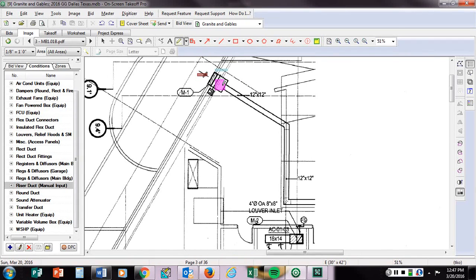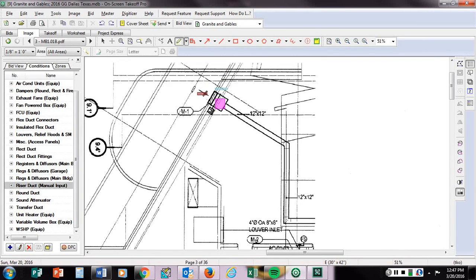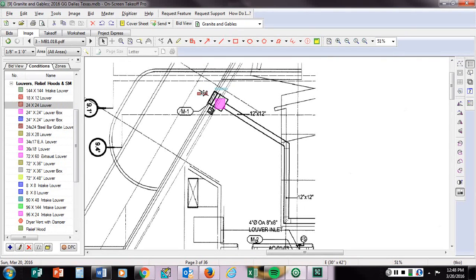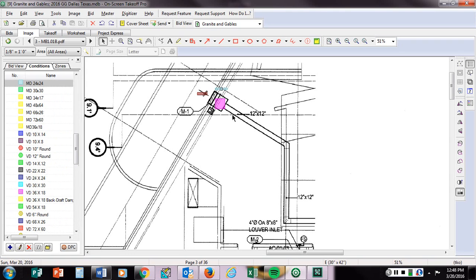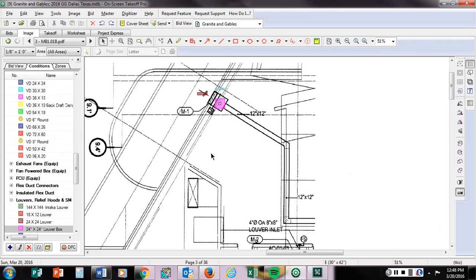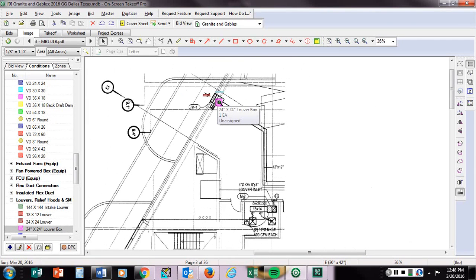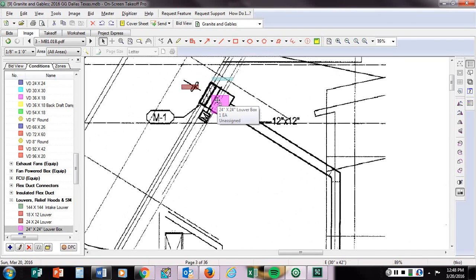Here we'd have a register box or a louver box. If you look at this M1 note, it says something like have a 4 square foot opening. So I went to pointer mode and clicked on this louver I already took off. This louver happens to be 24 by 24, or 2 by 2, or 4 square foot. We have a 24 by 24 motorized damper, and we also have a 24 by 24 louver box. I know they're not put into place real well - this was a leftover from yesterday. I just threw them on there to make sure we had them covered, to show you guys how to do those.